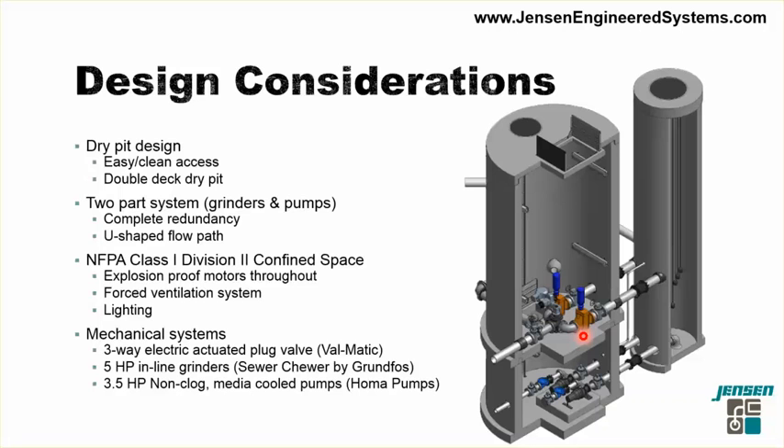The customer wanted complete redundancy, so each week the sewage is redirected between either the northern or southern grinder by a three-way electric-actuated plug valve manufactured by Val-Matic. Each week, for instance, if the southern grinder was running, it would be shut down, the valve would rotate positions, and the northern grinder would turn on. This is the inlet from the prison. Another challenge was that the entire dry pit was considered a Class 1 Division II confined space per NFPA, requiring all motors and electrical systems to be explosion-proof throughout.